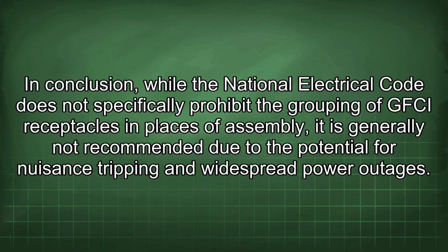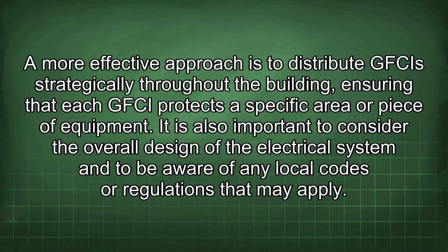In conclusion, while the National Electrical Code does not specifically prohibit the grouping of GFCI receptacles in places of assembly, it is generally not recommended due to the potential for nuisance tripping and widespread power outages. A more effective approach is to distribute GFCIs strategically throughout the building, ensuring that each GFCI protects a specific area or piece of equipment. It is also important to consider the overall design of the electrical system and to be aware of any local codes or regulations that may apply.